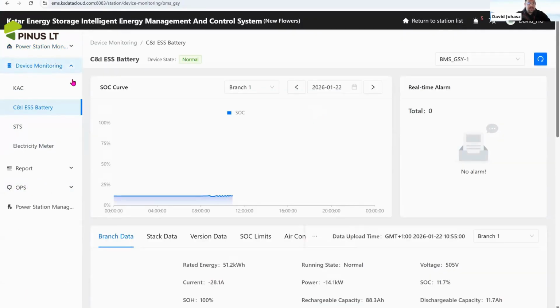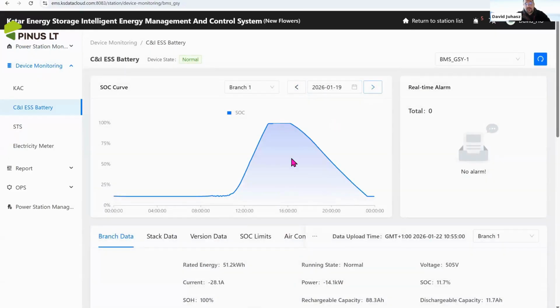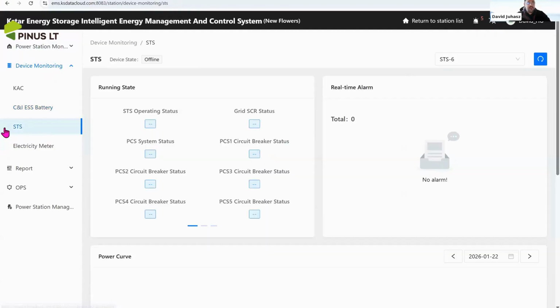We can see in the device monitoring when was this. So there was a sunny day. On the 19th, it reached the 100%, but on the next day it only went to 32.1% maximum SOC. So if there are 20 days, for example, in a row of not reaching the 100%, the cell voltage can go unbalanced.